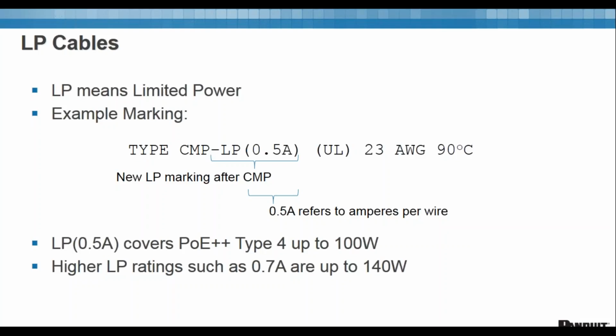Right now, you'd see, before, it would say type CMP, UL, 23 gauge, 90C. Now you're going to have type CMP-LP, and in parentheses will be the amps per wire, and then it'll go on as normal. So you might be saying, well, why is it 0.5 amps? I thought the new standard was about up to 1 amp. Because you take that value per wire. When I say 1 amp, that's per pair. The amps run on both pairs, so you divide by 2, it's a half amp per wire. And 0.5 amp covers Type 4 up to 100 watts.